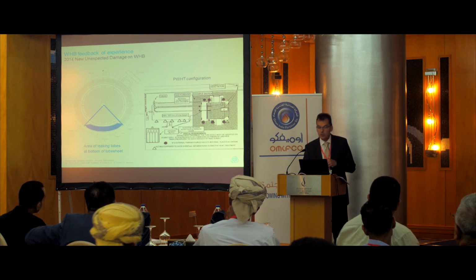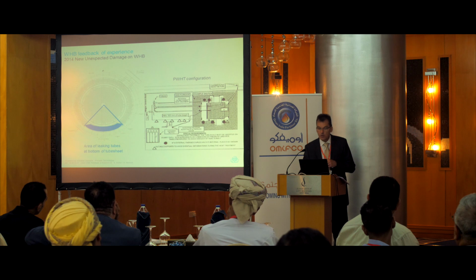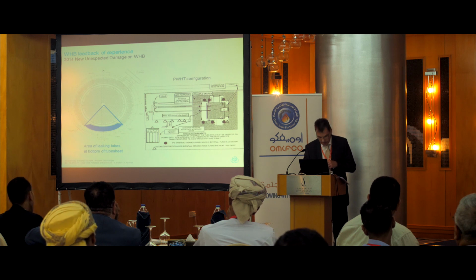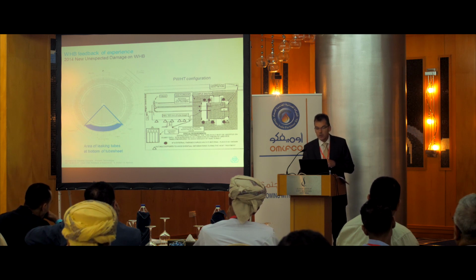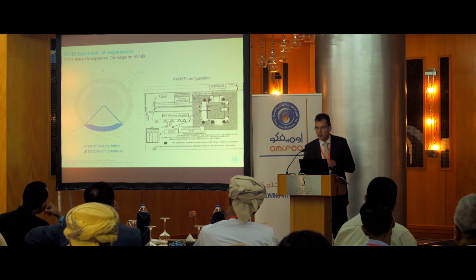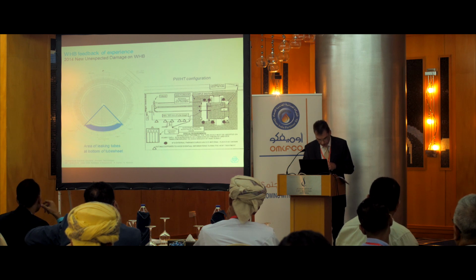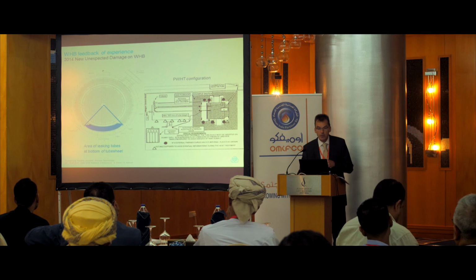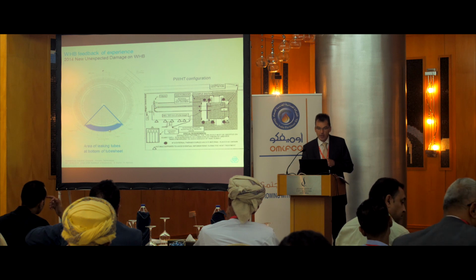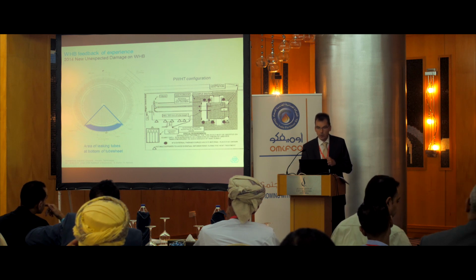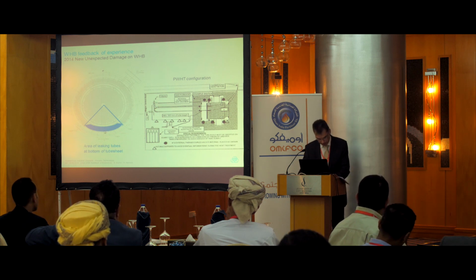And the nitrogen was not warm, it was cool nitrogen from the bottles. Our assumption at this time was that this affected the post-weld heat treatment of the tube-to-tube sheet at the lower part of this auxiliary shell near the tube sheet. This also fits with the location of the damages, which have all been here in the lower part of the tube sheet. This is also the location of the waste heat boiler inside the furnace.